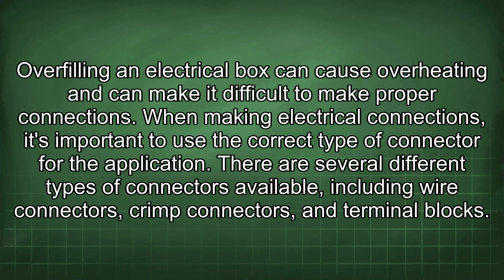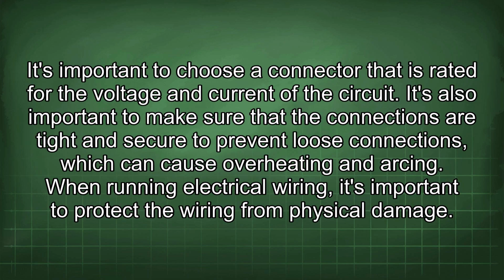When making electrical connections, it's important to use the correct type of connector for the application. There are several different types of connectors available, including wire connectors, crimp connectors, and terminal blocks. It's important to choose a connector that is rated for the voltage and current of the circuit. It's also important to make sure that the connections are tight and secure to prevent loose connections, which can cause overheating and arcing.